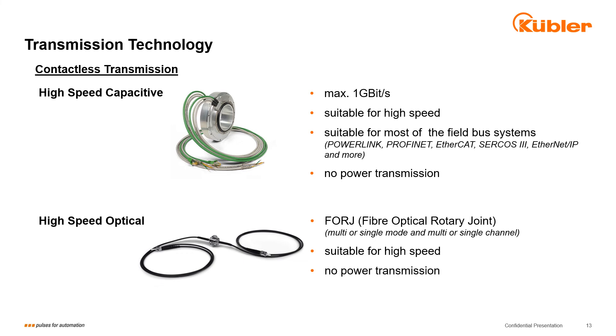Finally, I come to our contactless transmission technologies. Whereas in all previously mentioned variations transmission is via contacting elements, in these the transmission is completely contactless. As a result, both systems qualify for maximum speed and show no wear and tear at all. Firstly, we have our contactless capacitive transmission module designed for nearly all common fieldbus systems up to 1 Gigabit per second. Secondly, our fiber optical transmitter for multi- and single-mode transmission. Due to their non-contacting nature, both are of course not qualified for power transmission.